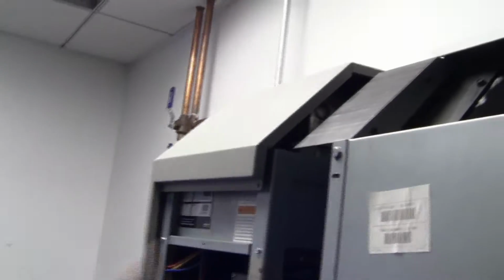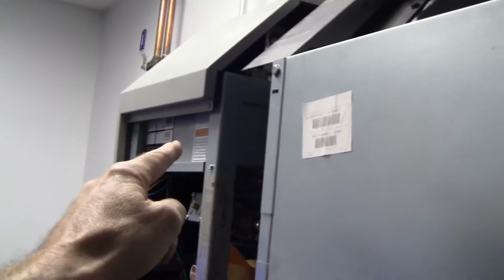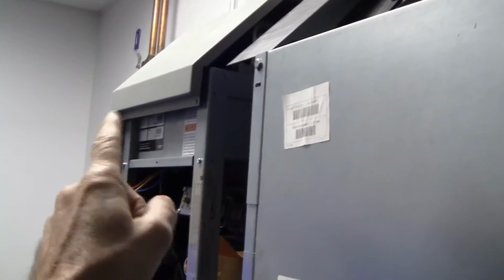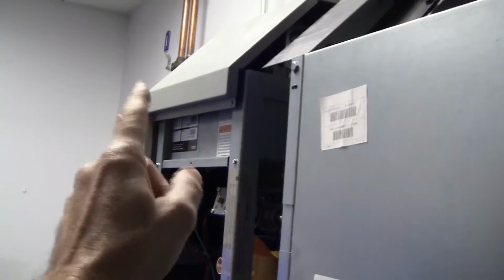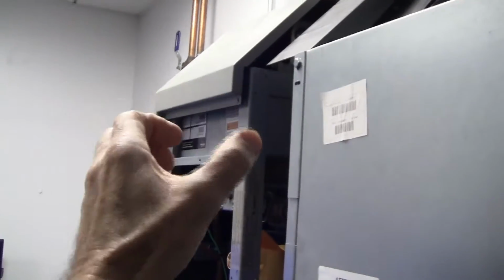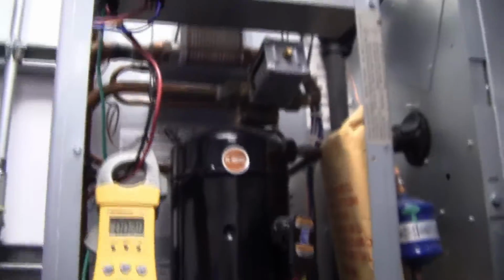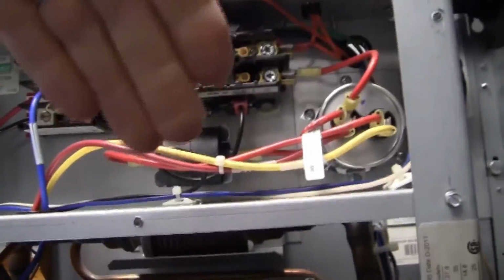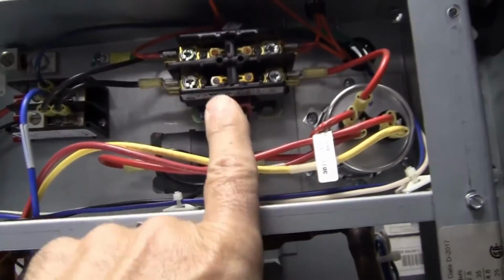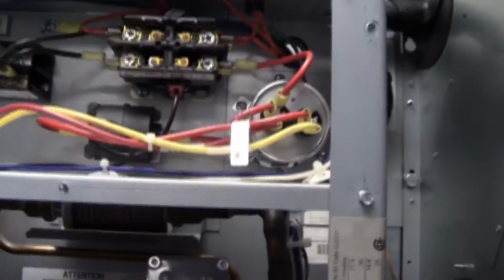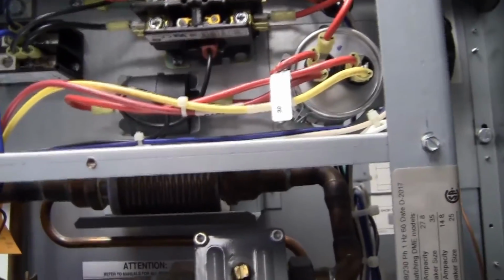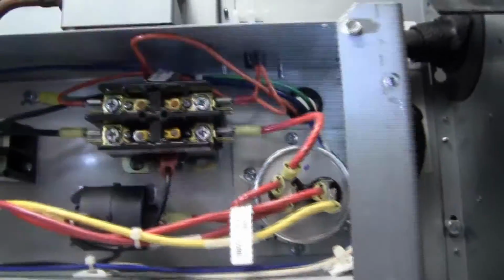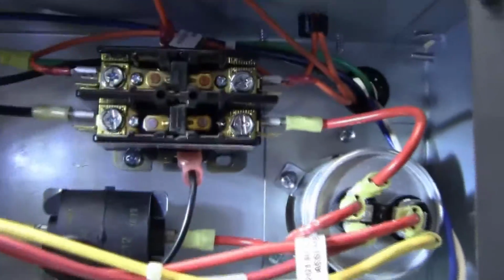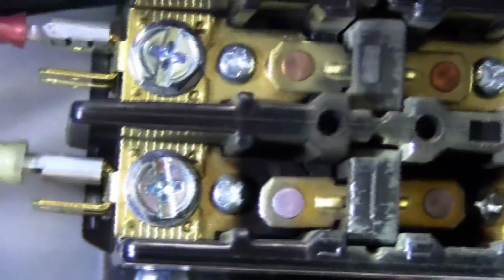I'm going to pull off this panel here and open up the electrical. We're going to get right to that contactor and verify that there's no 24 volts, but it looks like that contactor is stuck in the on position. Okay, here is your compressor. I took off the panel door that was right here. There's your compressor contactor, and you'll see on the bottom, hold on a second, look at all that blackened areas on those terminals right there.